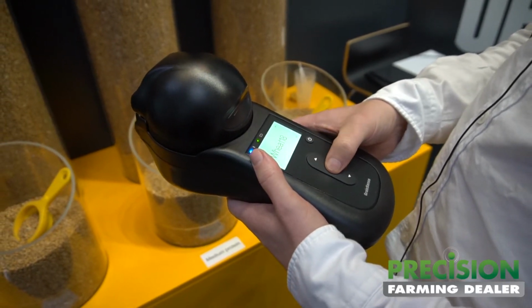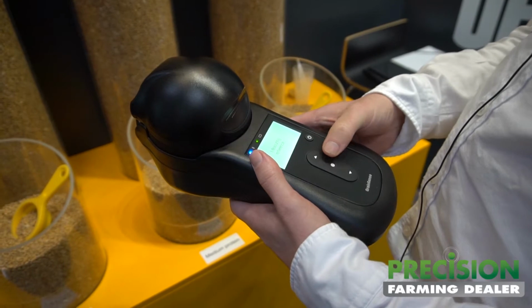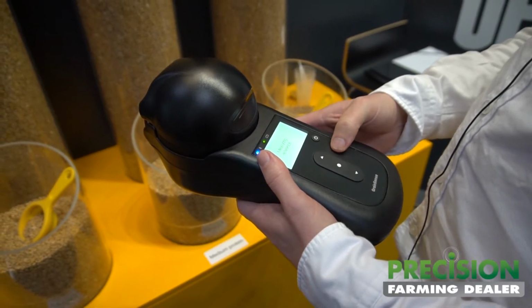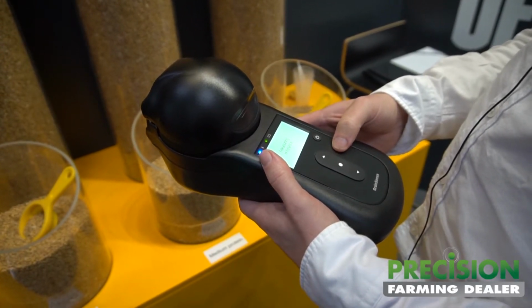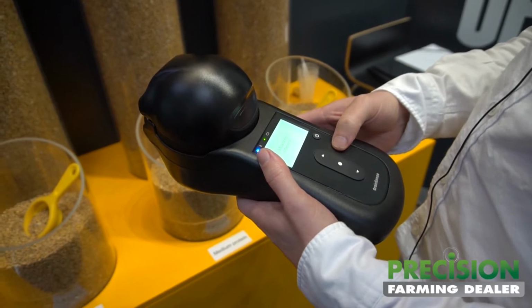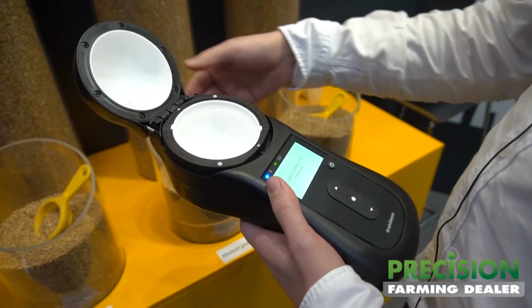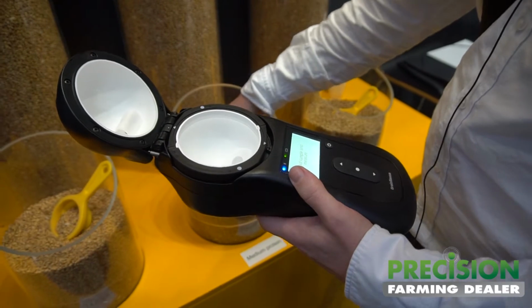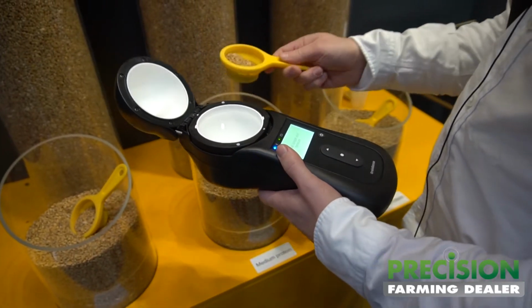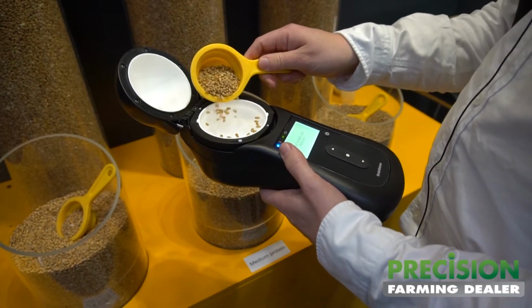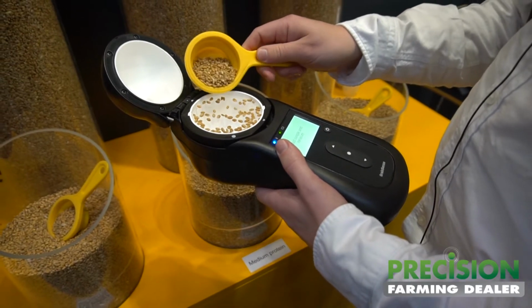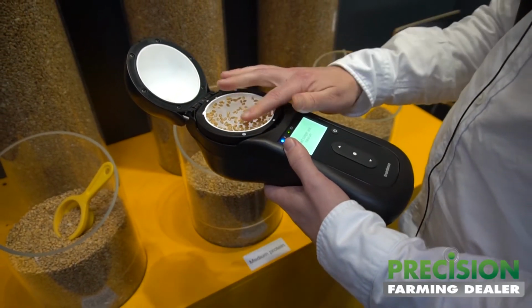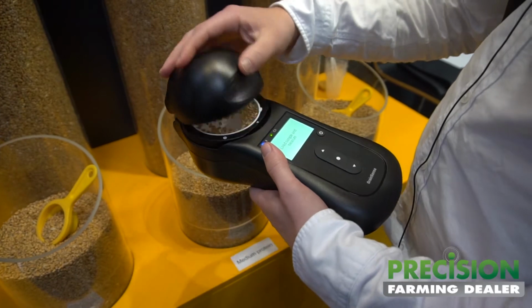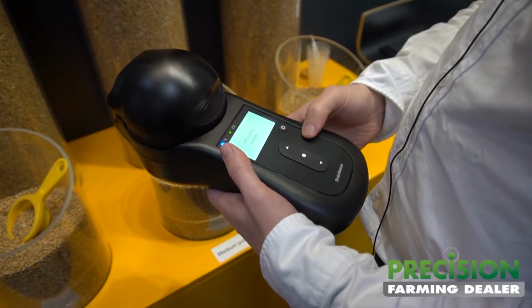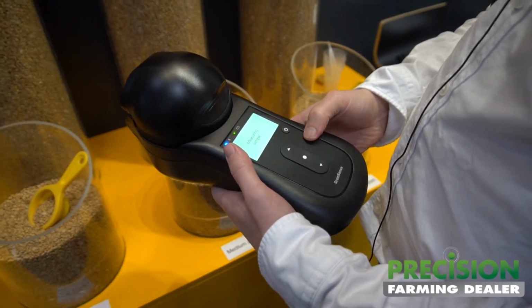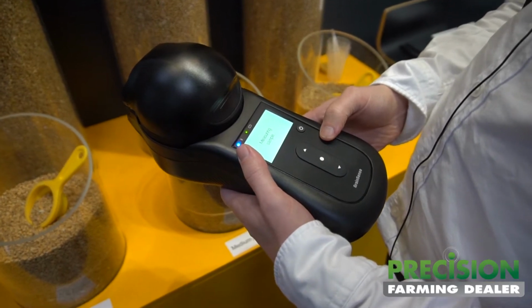Then you measure a baseline, so it does an empty reference measurement like a typical near-infrared transmission spectroscopy device does. Then you open, you take a small representative sample, you put it there, you close the lid, and you press, you wait a couple of seconds. It shows the moisture as well, carbohydrates and oil.